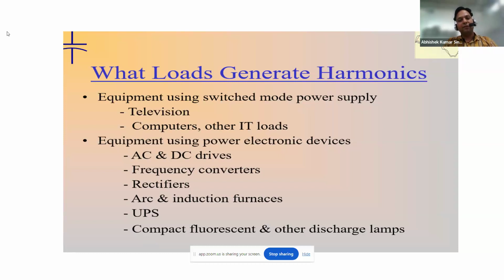So basically AC drive, DC drive, frequency converter, rectifier, induction furnaces, UPS, and CFL, and all those are basically non-linear loads which are producing harmonics. Now, harmonics, as we discussed, can be third harmonics, fifth harmonics, seventh harmonics, 11th harmonics. Okay, so we will understand in the next slide what is basically positive sequence, negative sequence, and zero sequence, and how we can calculate which type of harmonics shall be generated from this type of drive.